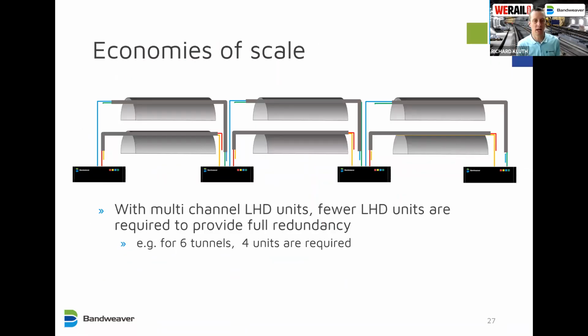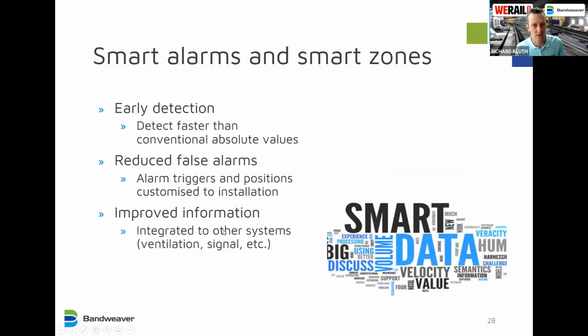And as we said, economies of scale, as you build up across the network with these systems, the ratios get even better. So this example shows 4 controllers and 6 channels. Apologies, there's a lot of wiring in here that is quite difficult to follow through, but I can run through it with anyone afterwards if they want. And you can see in each scenario, if you have a cut or a controller loss, you would have full coverage. So it really goes to show, as you build this up through the network, the economies of scale are really good for this technology.